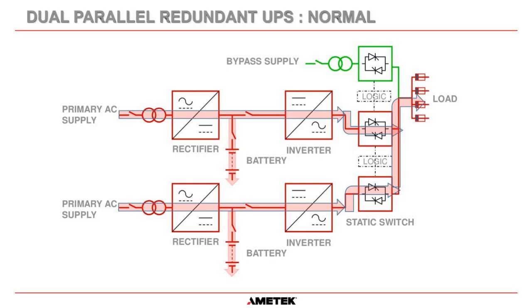There are also different designs of systems. The first — and most expensive but most reliable — is a dual redundant UPS. If your load requires 30 kVA, in a parallel redundant system you would have two 30-kVA UPS systems. They must be the same manufacturer and same model, because there is logic between the two UPSs to control synchronization so they can run in true parallel.